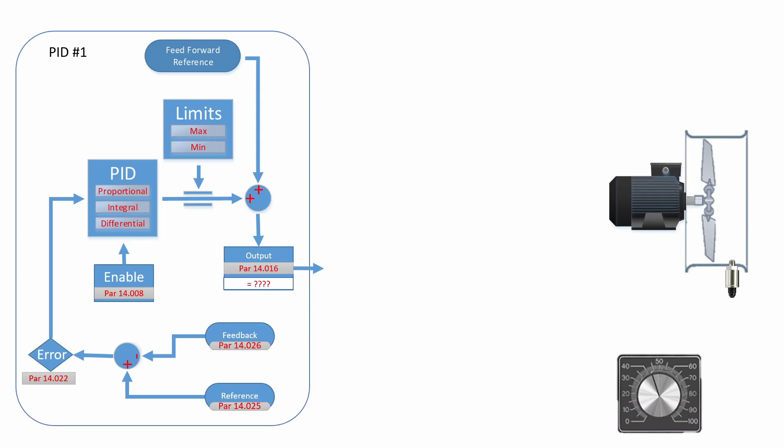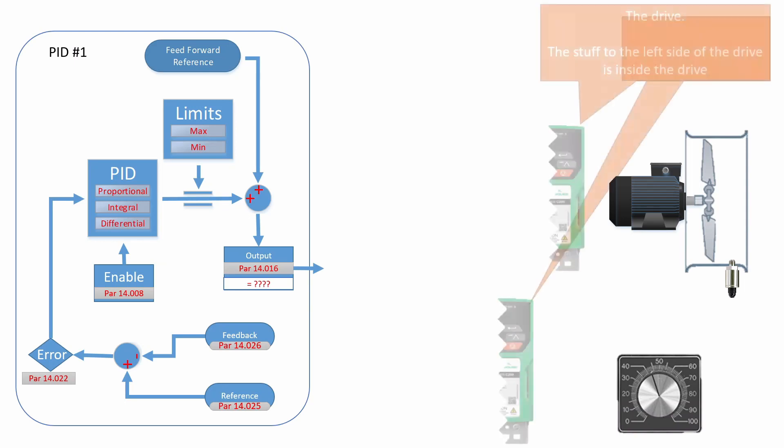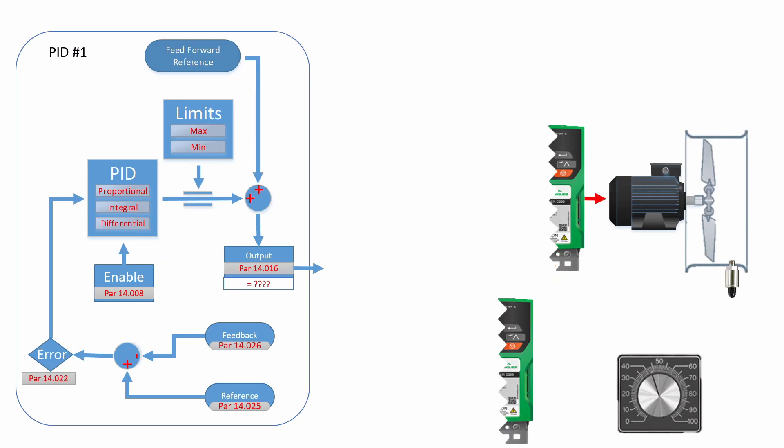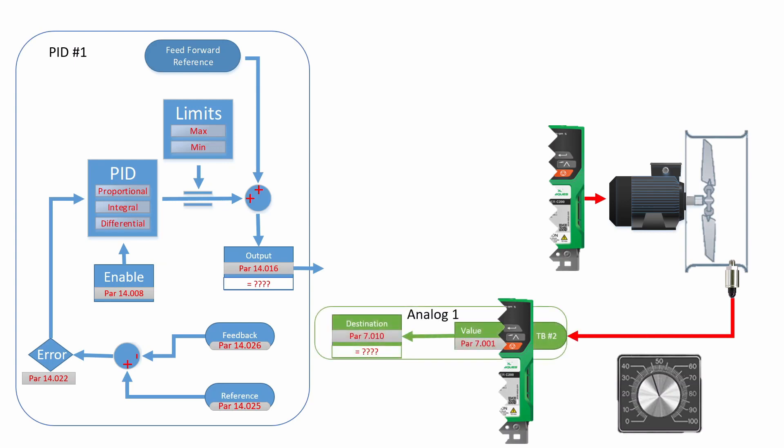So let's talk about wiring the drive. I'm going to use everything on the left side of the screen to represent stuff inside of the drive and everything on the right side of the screen to represent the wiring and the outside world. To wire the pressure transducer, you're going to wire it to terminal number two. The value of the pressure transducer will show up in parameter 7.001 as a percentage.